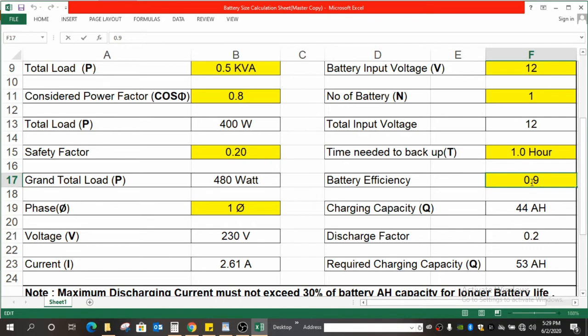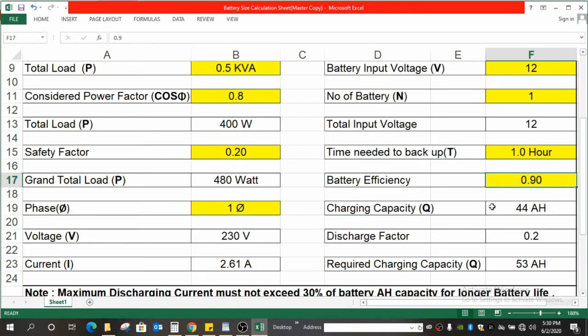Battery efficiency is that thing: if you are pushing 100 to a system and what is the system discharging, if it is discharging at 95, at that point the efficiency is 95 percent. In most of the batteries, the efficiency ranges from 0.85 to 0.92 to 0.95. On a safer side, on an average, I have considered 0.9. You can go by the exact data as you see on the battery specification.